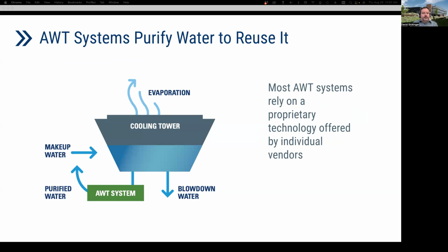So what are alternative water treatment, AWT, systems doing? They're basically purifying the water somewhere within the cooling tower system to minimize the amount of blowdown water, as reflected in this updated simple graphic. There are different approaches taken, but most AWT systems rely on proprietary technology offered by individual vendors. And as mentioned before, this guide has an appendix that provides a summary of the evaluated AWT technologies, along with links to past reports and presentations on each of them.